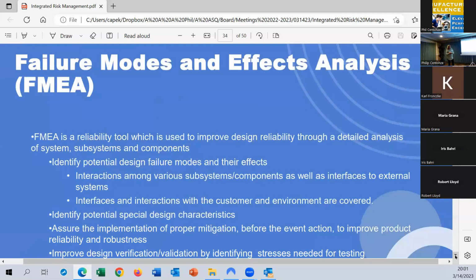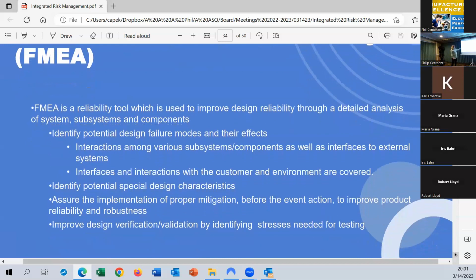Now, FMEA is typically a reliability tool, and it's used to improve the design reliability through detailed analysis of the system, subsystem, the component. You can do process FMEAs, or there are different types of FMEAs. And in an FMEA, you identify the failure modes and their effects on the system, and then you try to mitigate those failure modes. This can help you identify special or critical quality attributes of a device that then you can control through production, right, or through your supplier to ensure that those critical quality attributes are always met.